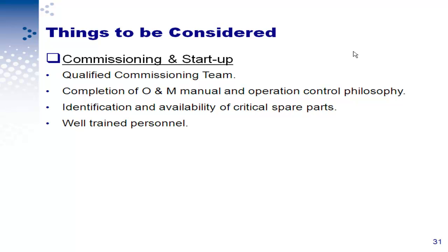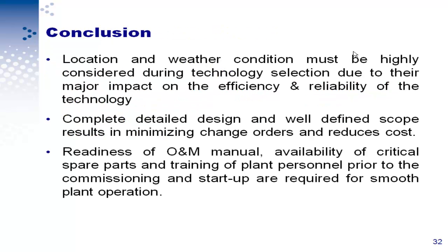You need to provide complete and precise construction specifications, well-defined responsibilities between client, contractor, and vendor. During construction: have a realistic schedule — we had six months of delay — a qualified construction contractor, and a strong inspection team. During commissioning and startup, have a qualified commissioning team and ensure the O&M manual is available before you start the plant. In conclusion: location and weather conditions must be highly considered during technology selection due to their major impact on efficiency and reliability. Complete detailed design and well-defined scope minimizes change orders and reduces cost. Availability of critical spare parts and training of plant personnel prior to commissioning and startup are required for smooth plant operation.